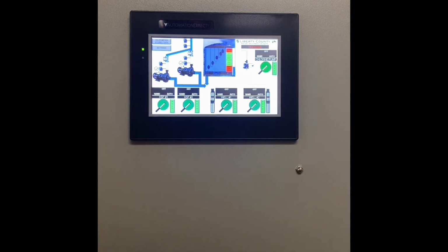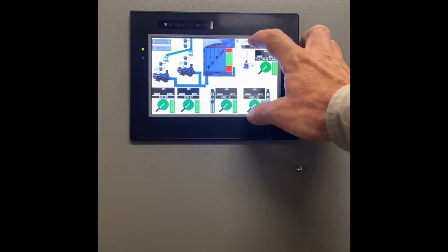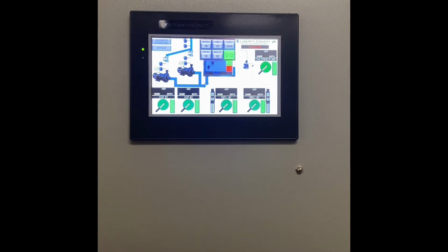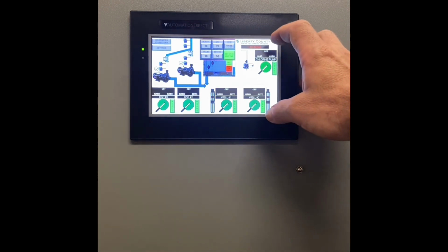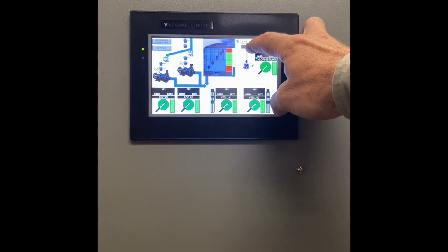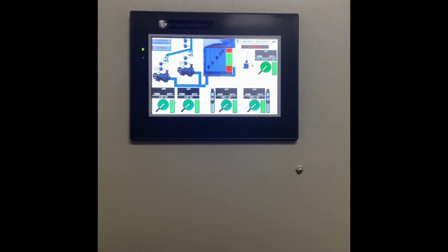And there it is green. You'll notice the other 4, they all work exactly the same. Now, the only other thing on the right-hand side of the screen, and it really doesn't have a lot to do with the control algorithm, is you'll notice that we have a clock with a date and time on it. If I touch that date, I will bring up an input number pad where I can change the date and time, and then when I hit set date and time, it will enter. I can touch it again and it disappears.